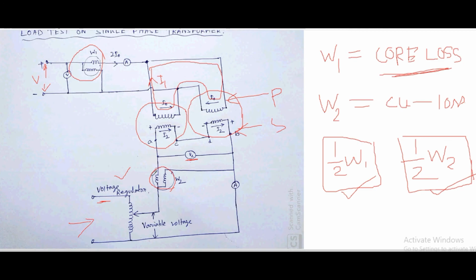Number two, if you want to know the temperature rise, then the two transformers are kept under full load condition for several hours till the maximum stable temperature is reached. But if you see, in this primary winding the current is I1 minus I0, whereas here the current is additive. So though these two transformers are identical, they do not operate under identical conditions. One may have slightly less temperature than the other. So this is the test for a single phase transformer.